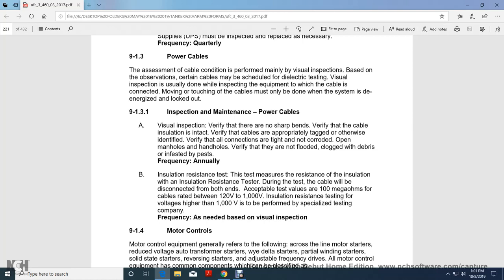Visual inspection: verify that there are no sharp bends. Verify that the cable is intact and appropriately tagged. Identify that all connections are tight and not corroded. Open manholes and handholes and verify that they are not flooded or clogged with debris, and that drainage is not blocked, annually.